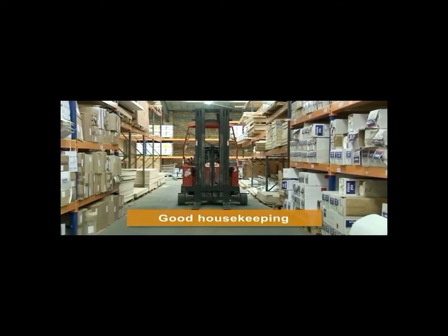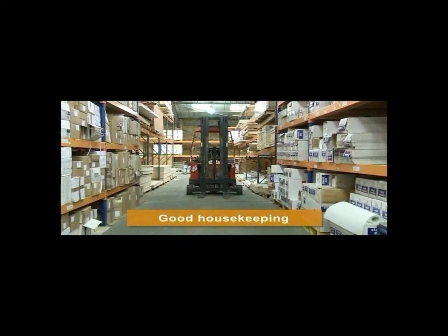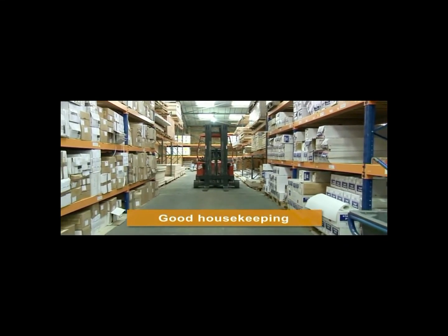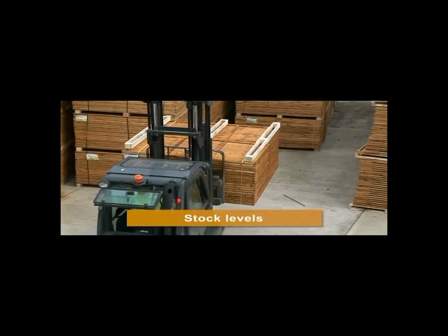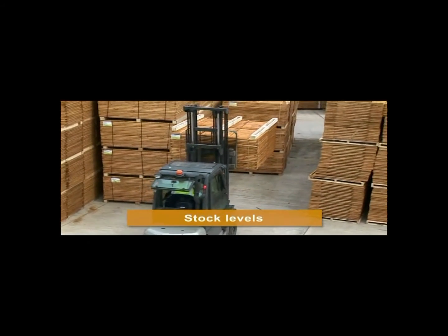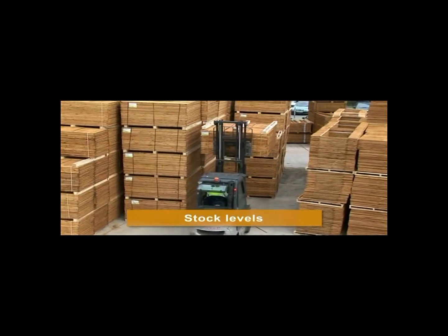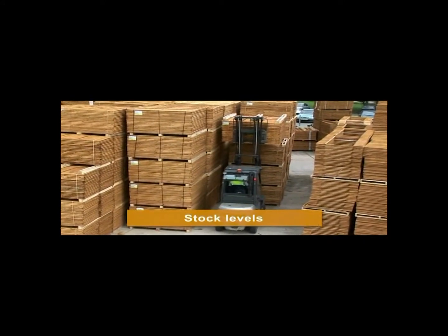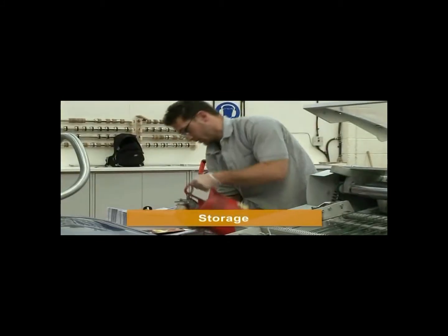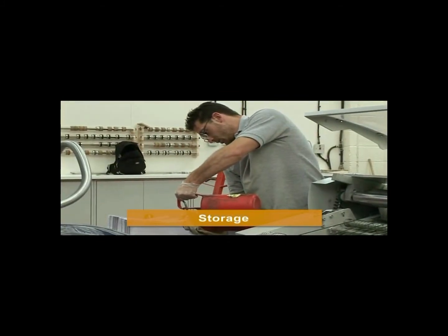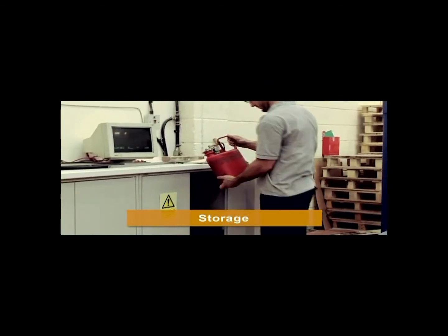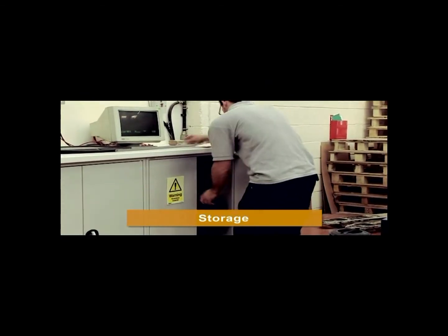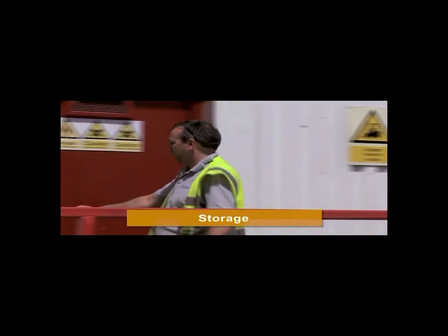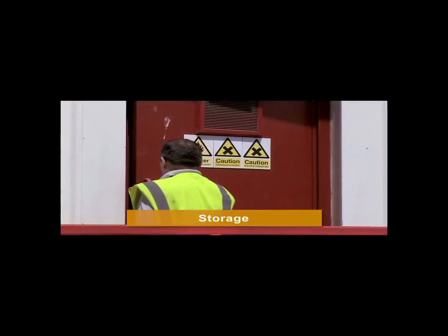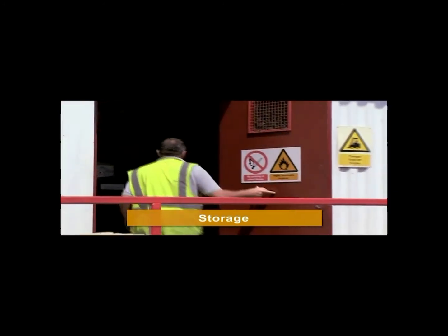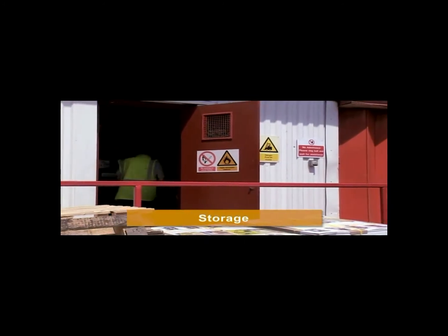If possible, use dedicated storage areas well away from potential ignition sources. If your stock is easily ignited or highly combustible, consider whether you could reduce the amount held on your premises by ordering smaller quantities more often. If you have to use flammable liquids or gases, only store the minimum at a work area, in appropriate containers and cabinets. Use dedicated safe and controlled storage for all flammable and potentially explosive materials. Wherever possible, these areas should be outside the building.